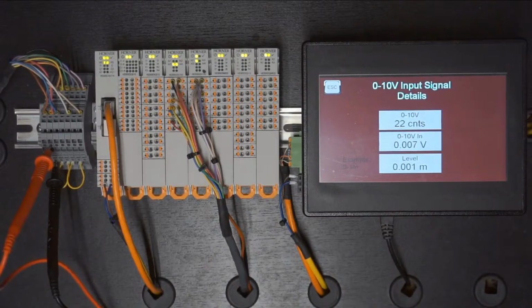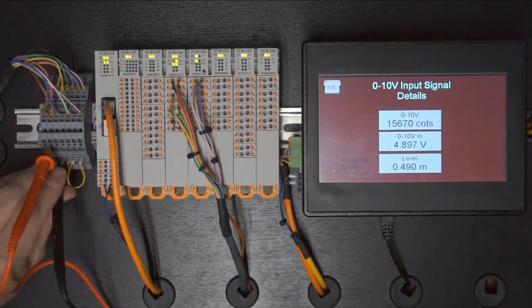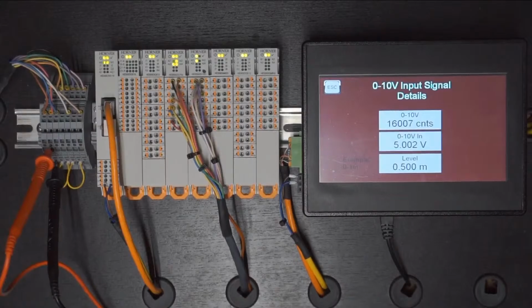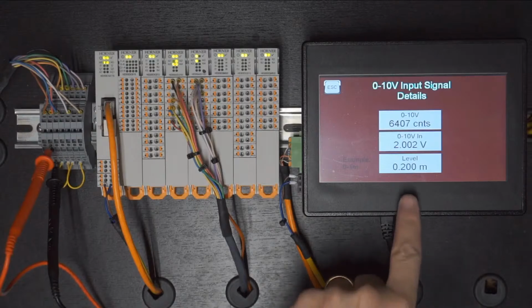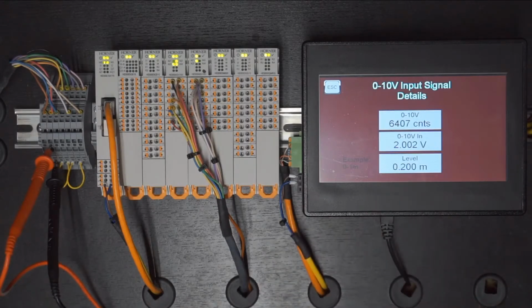Obviously, I don't have a good connection. There we go. I have a little bit of trouble with these terminal strips. I won't tell you who the manufacturer is. But anyway, now that I've got a good connection, you can see mid-range, I'm within a few counts of 16,000. If we go down to, say, 2 volts or 20%, we should see it react appropriately, and it is. And I'm simulating, say, a level of 0 to 1 meter, and at 20%, I'm at the 0.2 meter level. We'll go up to a full 10 volts on the simulator and watch it go up to 32,000-ish counts. Okay, so that's voltage.